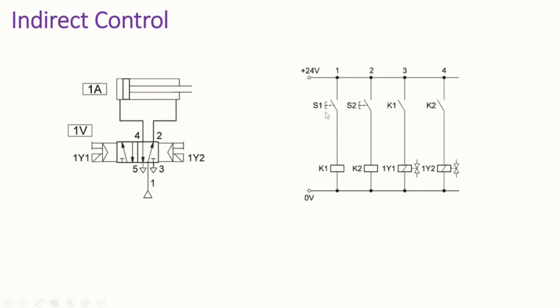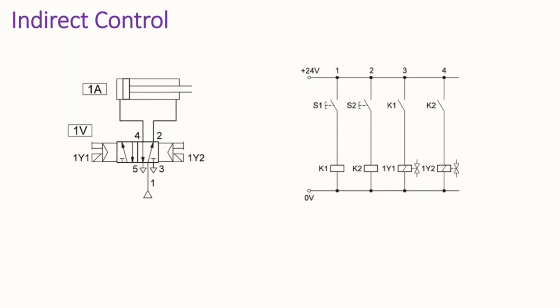Whenever we turn on S1, K1 is energized, the make switch closes, solenoid 1Y1 is energized, and the valve is electrically activated and shifted to the second position. Air passes and the piston inside the cylinder starts advancing. Once it reaches the fully advanced position, if we turn on S2, K2 is energized, this make switch closes, 1Y2 is energized, the directional valve shifts to its first position, and the retraction process starts. This combination of switches, relays, make switches, and solenoids is called indirect control.